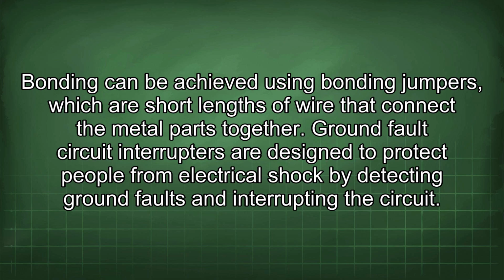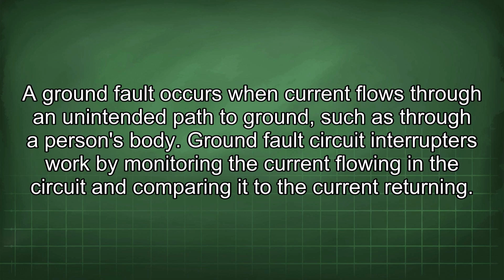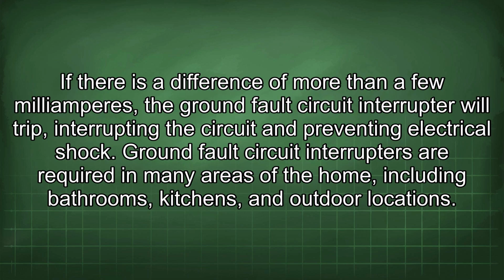Ground fault circuit interrupters are designed to protect people from electrical shock by detecting ground faults and interrupting the circuit. A ground fault occurs when current flows through an unintended path to ground, such as through a person's body. Ground fault circuit interrupters work by monitoring the current flowing in the circuit and comparing it to the current returning. If there is a difference of more than a few milliamperes, the ground fault circuit interrupter will trip, interrupting the circuit and preventing electrical shock. Ground fault circuit interrupters are required in many areas of the home, including bathrooms, kitchens, and outdoor locations.